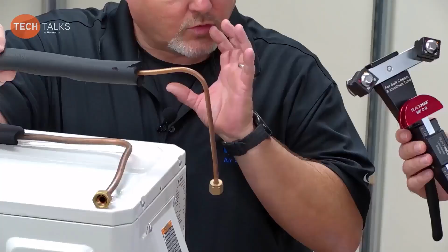That's why I say these mini splits work great, but it's all about flow and refrigerant, and we want every single bend as proper as you possibly can. If you want no issues with the equipment and want to put that in for your customer without any problems, I can't stress enough how important it is to go that extra mile - have the right tool, bend the tubing with the proper tool.